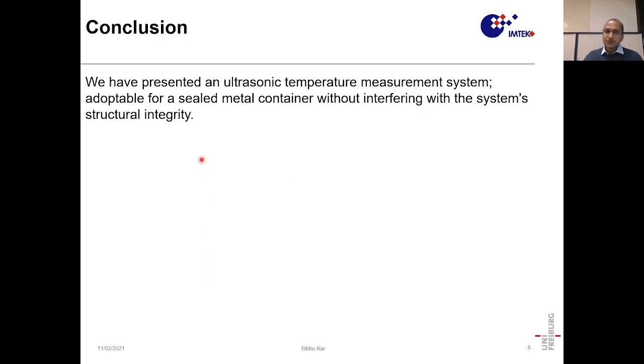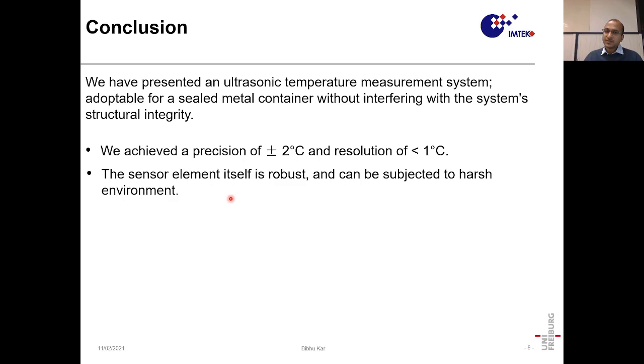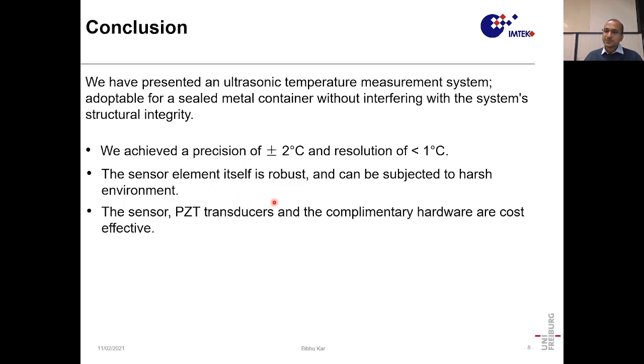And as a conclusion, we have presented an ultrasonic temperature measurement system adaptable for a sealed metal container without interfering with the system's structural integrity. We achieved a precision of 2 degrees Celsius and a resolution of 1 degree Celsius. The sensor element itself is robust and can be subjected to harsh environments. The sensor, the PZT transducer, and the complementary hardware are very cost effective.